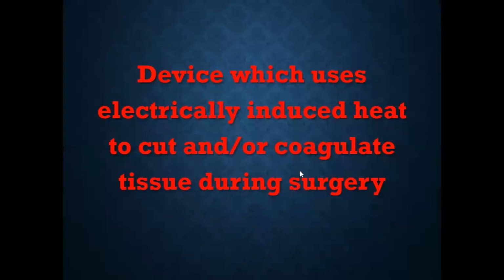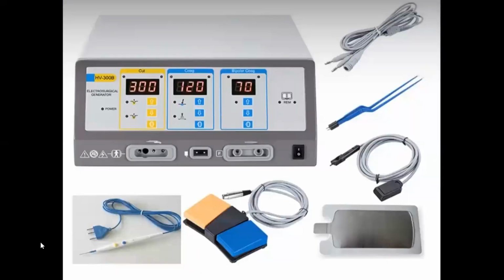So what is diathermy? It's a device which uses electrically induced heat to cut and or coagulate tissues during surgery. This is the application of diathermy. So we have monopolar and bipolar. Monopolar, you have seen, there's only one pole, one end like a pen. It has two knobs here, one to cut, another one to coagulate. So it can cut and coagulate. But bipolar, like a forceps, has two poles, two ends. It only coagulates, it doesn't cut.